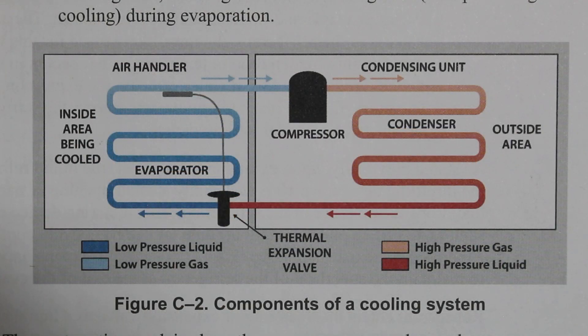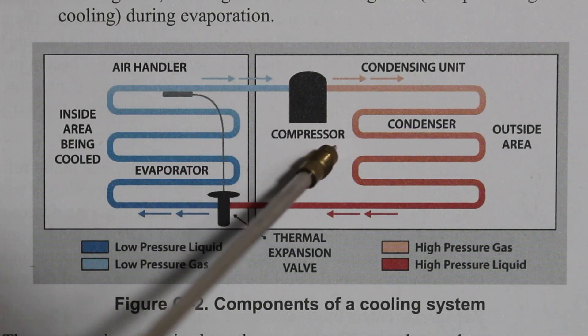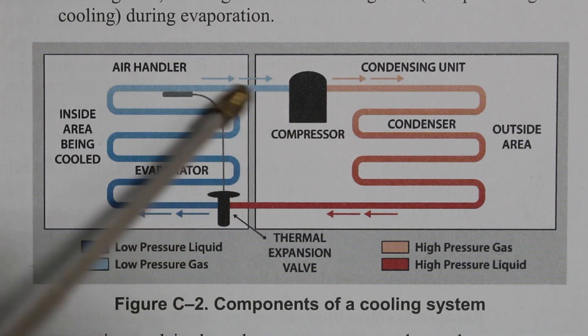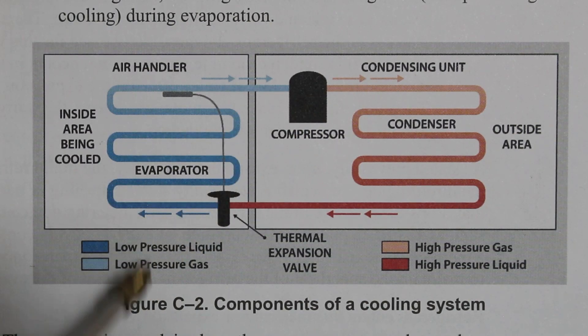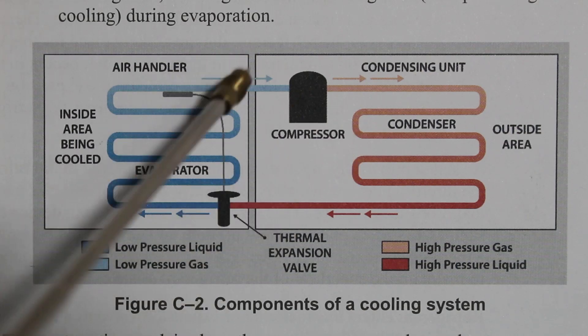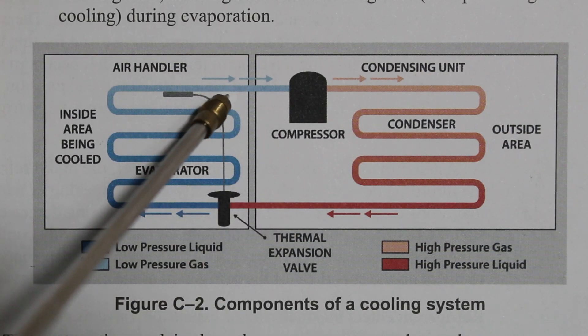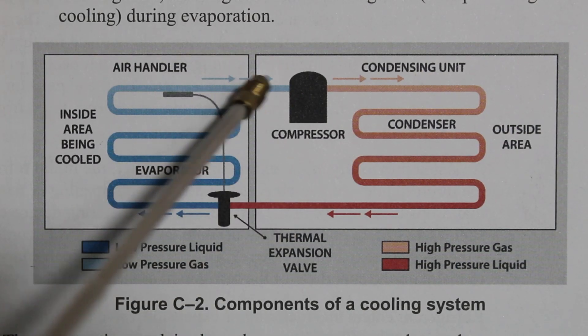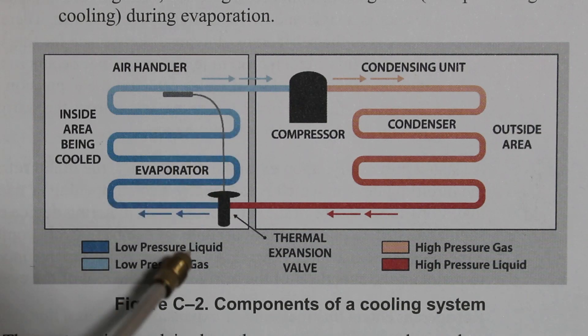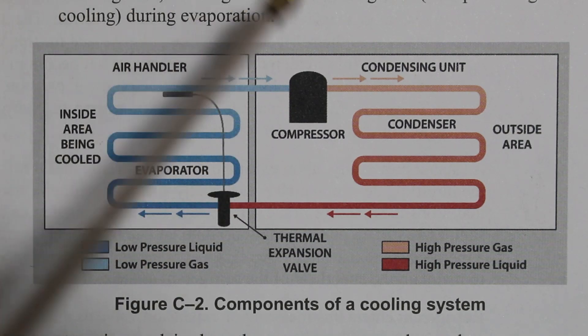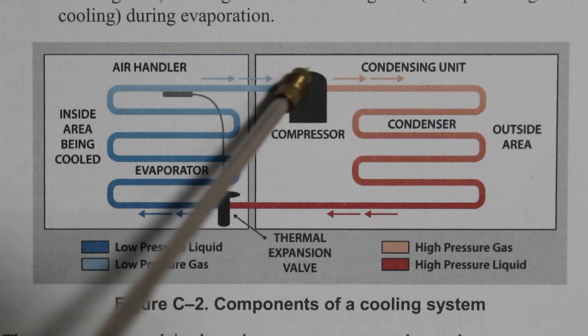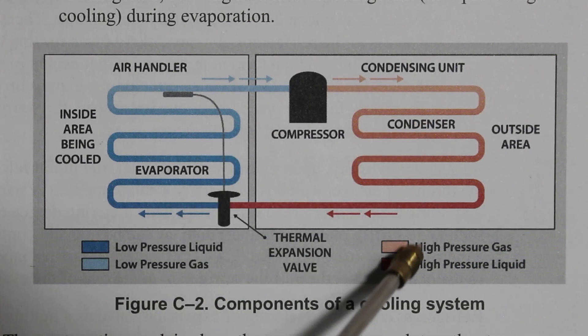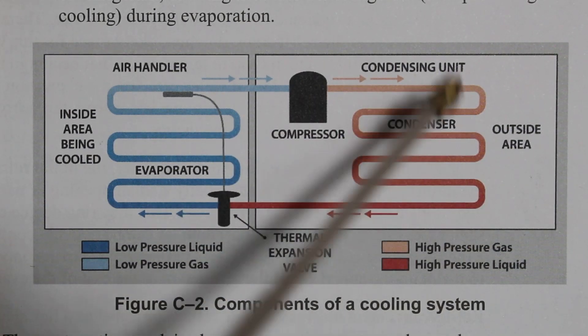Let's begin our lesson with our compressor. Our compressor is also known as a vapor pump. Entering our compressor we have a low pressure gas — specifically a low pressure, low temperature, superheated vapor. A vapor and a gas are the same thing; I just prefer to use the word vapor. So leaving our compressor, if we follow our color code, we have a high pressure gas.